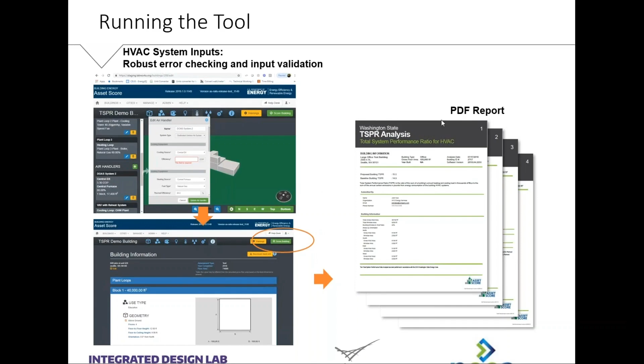So this is just an example of a large office building which was analyzed using the tool. The first result that you see is for the Washington State Energy Code baseline, which is a water source heat pump with DOAS and ERV. And this receives a TSPR of around 15. Again, we're using carbon emissions for electricity and gas as defined in the code. And we analyzed the same building with several different HVAC systems, a minimally compliant fan coil unit with DOAS ERV, where the DOAS had a sensible effectiveness of 50%. As you can see, this minimally compliant fan coil unit does not meet the TSPR requirements, and we had to improve the fan coil unit with improved efficiency, higher effectiveness DOAS, and then improved chilled water and hot water pump power to get it to comply.